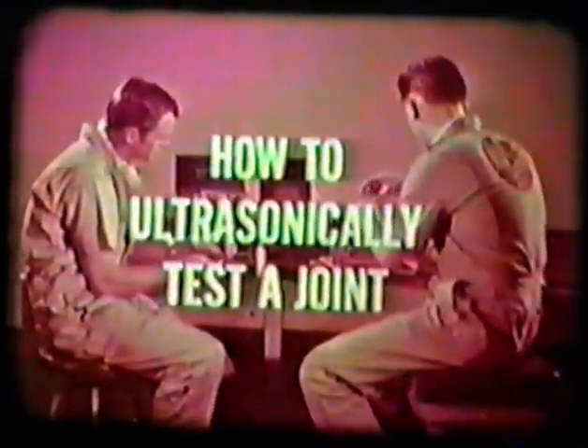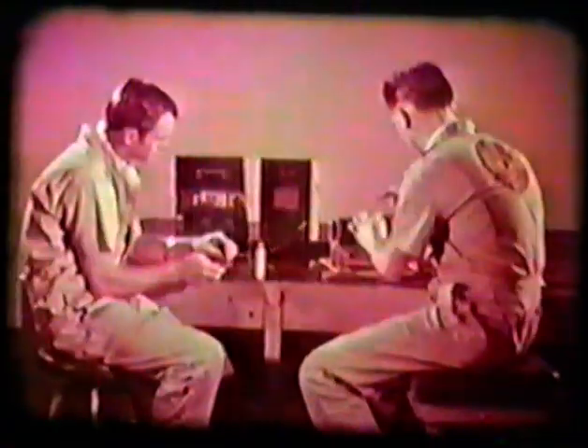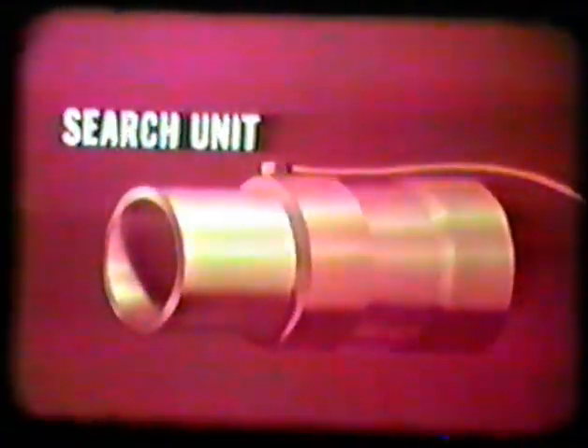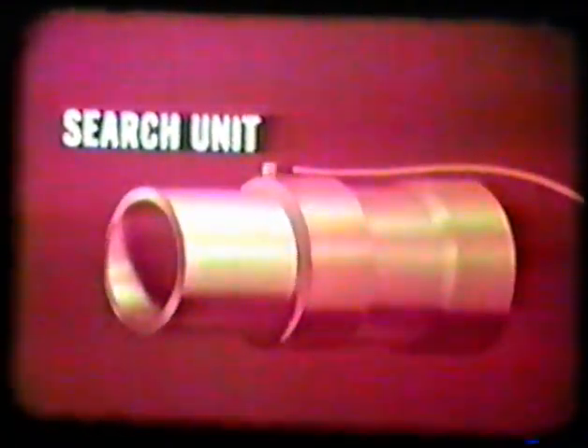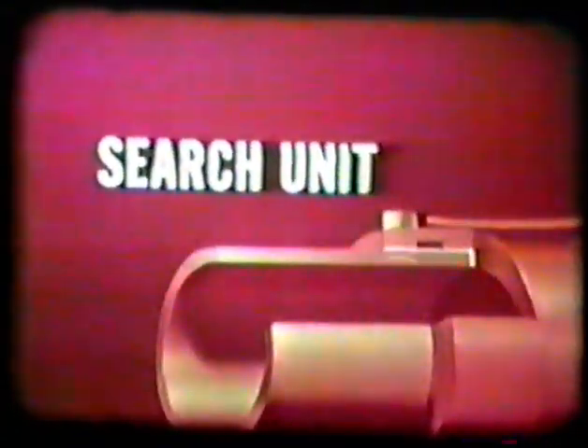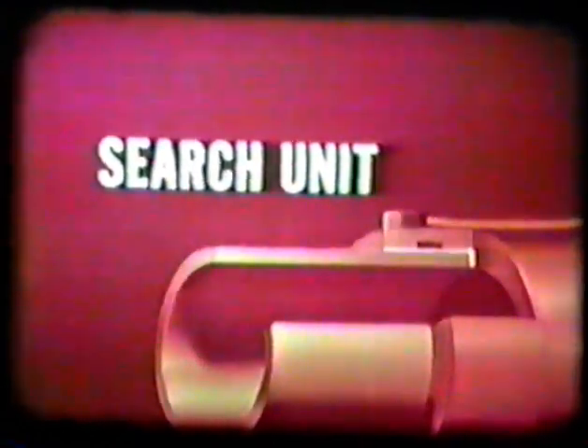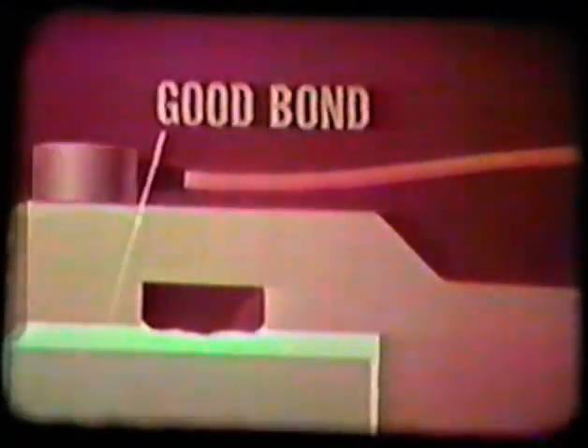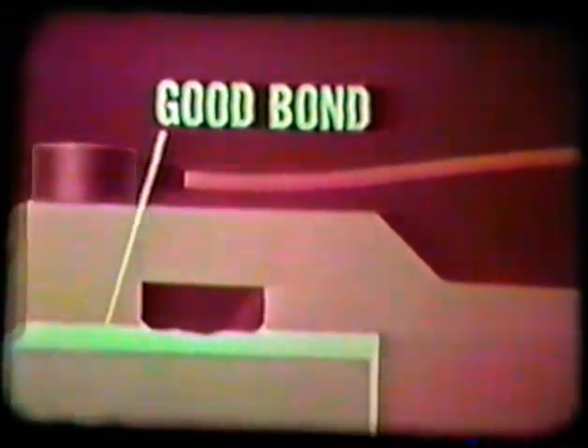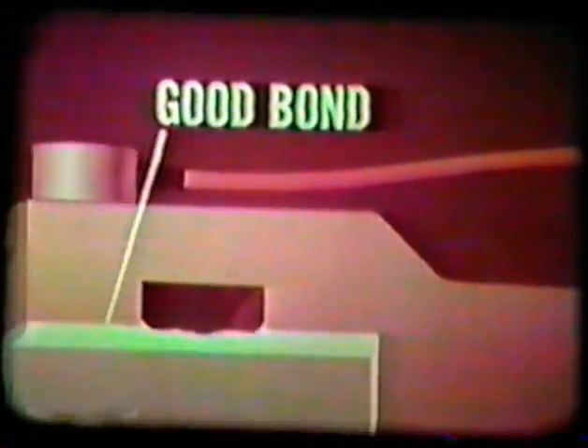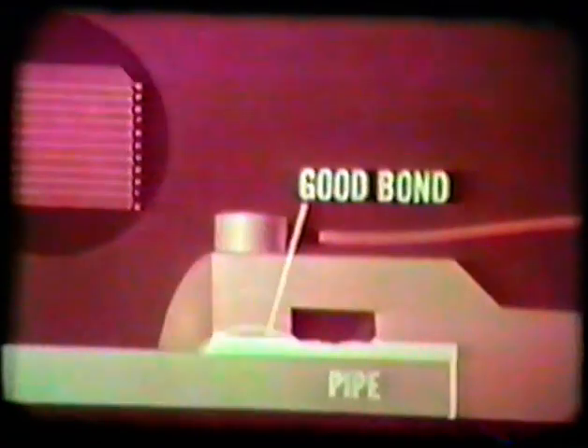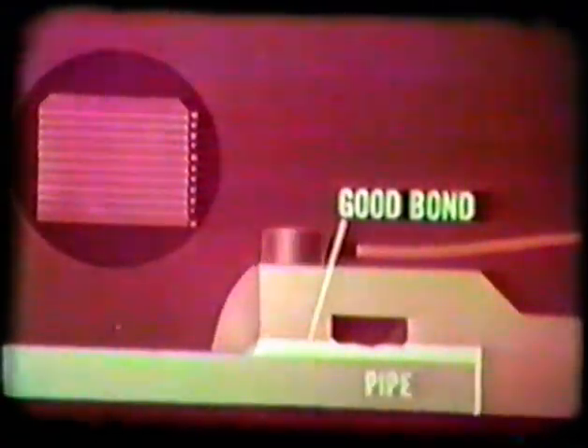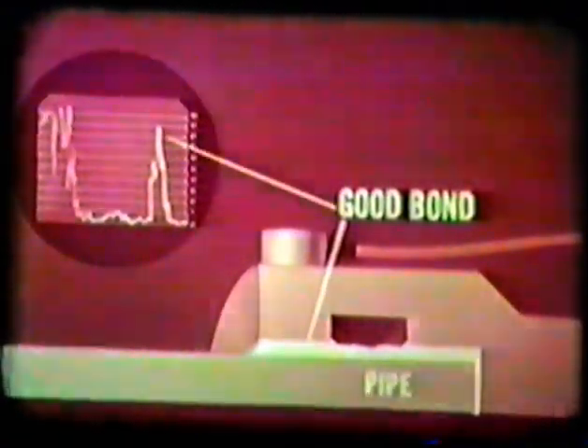The ultrasonic test, or UT, uses a principle similar to the sonar employed aboard submarines to detect enemy targets. The operator moves the crystal search unit around the joint. High-frequency electric impulses make the search unit mechanically vibrate. The vibrating unit thus transmits sound waves into the fitting and pipe of the joint being tested. If the alloy bond is good in the area being tested, the waves penetrate to the inner surface of the pipe before being reflected back.